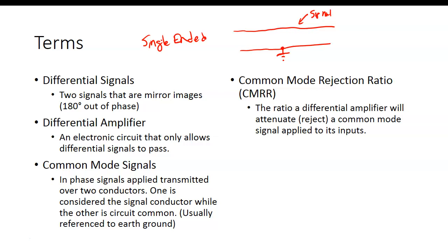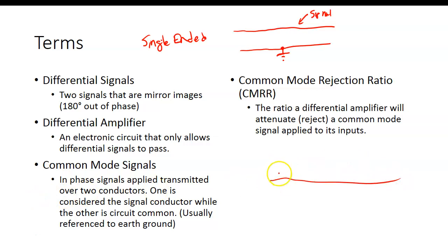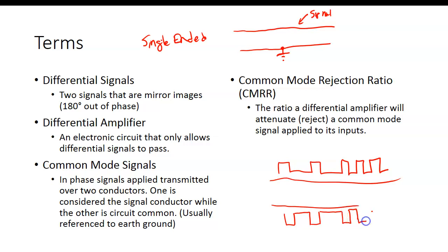Differential signals use two signals that are mirror images of each other, 180 electrical degrees out of phase. We send digital information - one wire sends a signal, and the other conductor has the same signal but 180 degrees out of phase. So we always have a difference in potential. Double-ended differential signals don't use a ground and don't use a common - they're actually out of phase with each other.